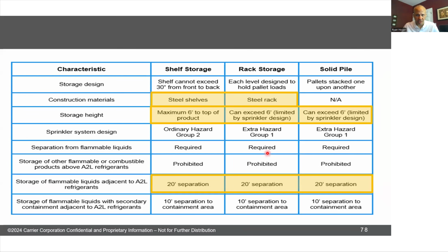Storing refrigerant in your building. For the most part, the simple answer is keep different chemicals separate from each other, right? Don't put the A2Ls with the propane. Don't put it with the acetylene. Don't put it with the A1s. Just keep everything in its own area of the building, right? Keep things separated. That way there's less issue. Don't put it by flammable stuff. Keep a fire extinguisher in the area, right? Just general good rules like that. It's kind of the quickie answer, if you will.